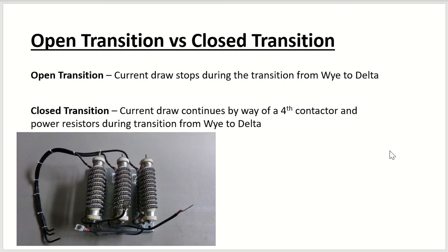The term you may hear is open transition versus closed transition, and this is a whole other topic in itself. But just a quick explanation. Open transition means that the current draw will stop during the transition from Y to delta. So you have it start in the Y configuration, you completely remove the power, and then you re-energize the two contactors to put full voltage on the windings. That goes, put it in the delta configuration, and it goes to full voltage.